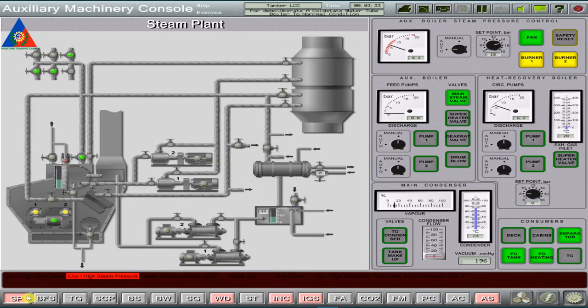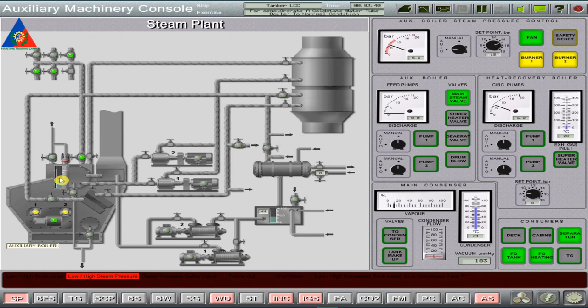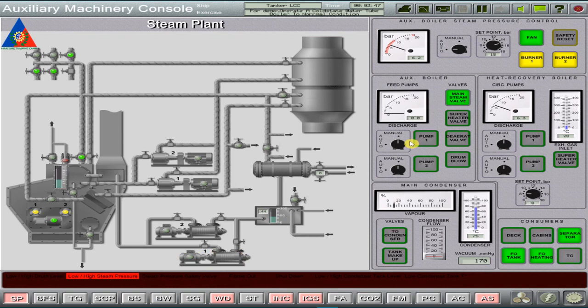Checking the steam pressure on the boiler drum, which is still at low pressure, we need to start auxiliary boiler feed pump number 1 and set it to auto mode to prevent low water alarms as well as prevent internal water tube damage.